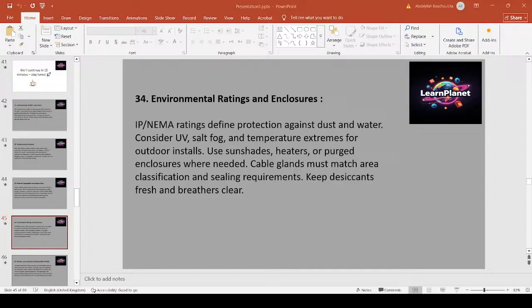Choose enclosures with appropriate IP ratings for dust and water ingress. Include UV and salt fog considerations for coastal sites. Use sunshades, heaters, or purged enclosures for extremely high and low temperatures and for condensation control. Cable glands must be compatible with area classification and ensure proper sealing. Keep desiccants fresh and check breathers during maintenance. Example: outdoor analyzer cabinets often require IP66 NEMA 4X with purge and heater for desert summers and winter nights.